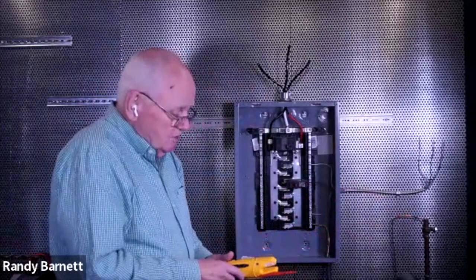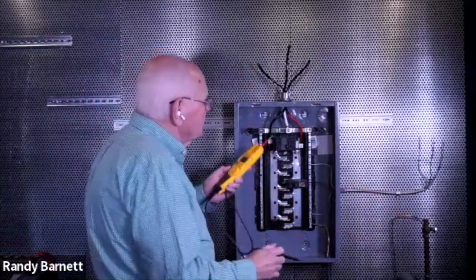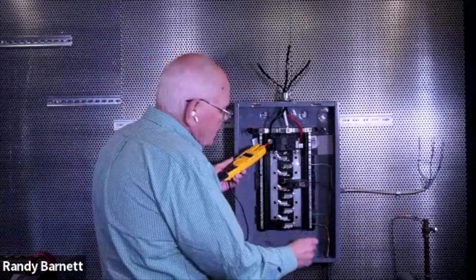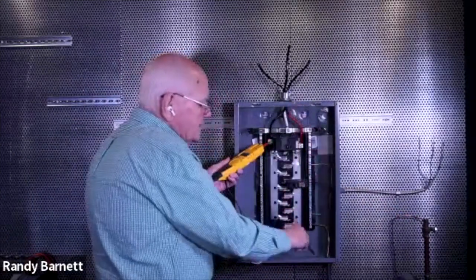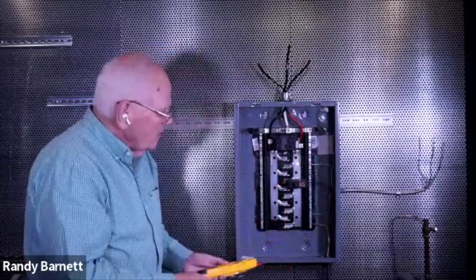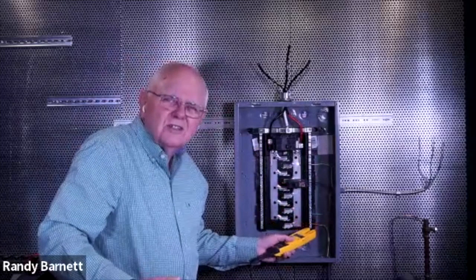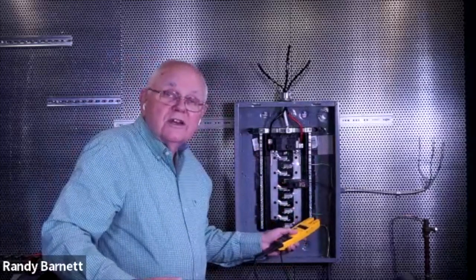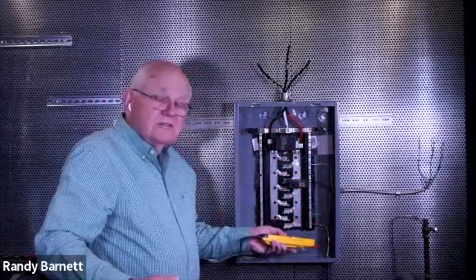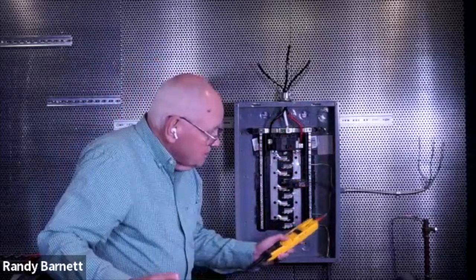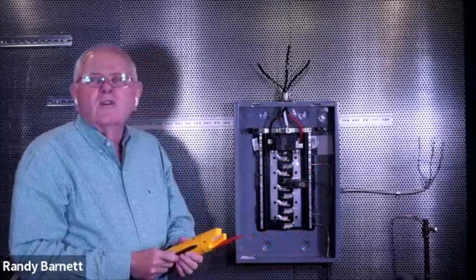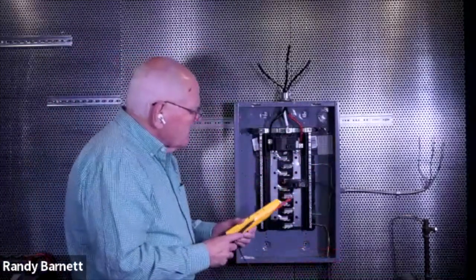If I didn't have a grounding electrode conductor, and I were trying to read from phase to ground on my cabinet somewhere, voltage would be all over the place depending on the load in the system. So it stabilizes our voltage to earth during normal operation. Also, something else very important that this grounding electrode conductor does for us is that it will divert any voltage surges that come through the system into the earth. Well, not all of it. Sometimes we can still get voltage surges downstream into our system. So we see overvoltage protection requirements in the National Electrical Code as well. But let's get back to our grounding then.